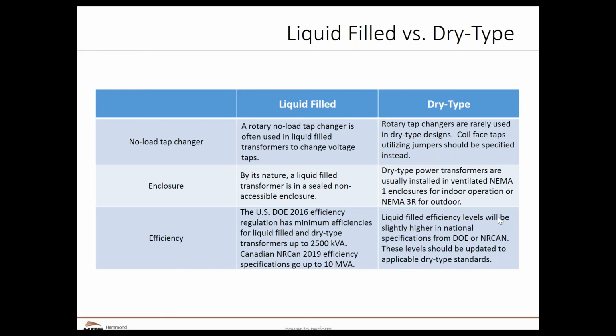So when some people say I want a no-load tap changer, that's because I have a problem bringing additional wires through the transformer sidewall and potential for leaks that I don't want to encounter, and I can fix that. I can mitigate that by having a no-load tap changer submerged in the oil. I don't need to do it with a dry type. Okay, and we sometimes have people say, well, I still want the no-load tap changer.